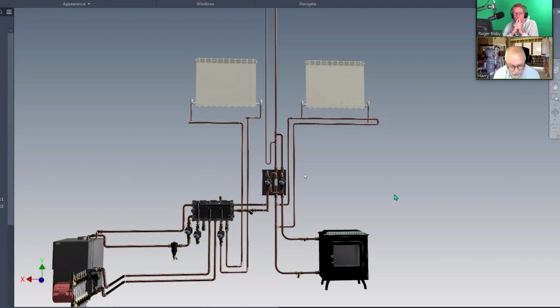About 4 or 5 years ago, I was a member of so many different groups, and every day someone was saying, look, if you put close coupled T's here, and use the pump here, and use this valve and put in a 3-port... they were trying to figure a way to stop all these system problems. There were so many people objecting, saying I've done that before and it didn't work. Then someone came up with a brainwave: why don't we just not have zones? Then everything runs around forever and nothing can happen.